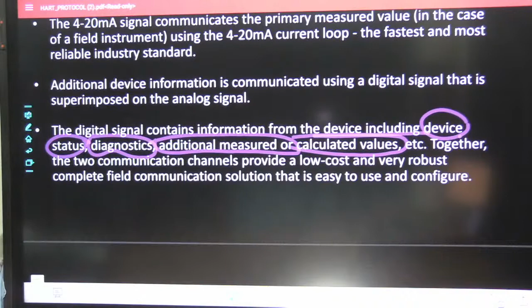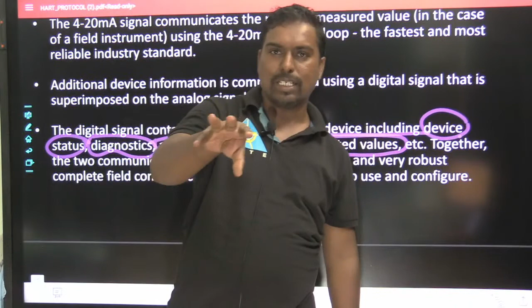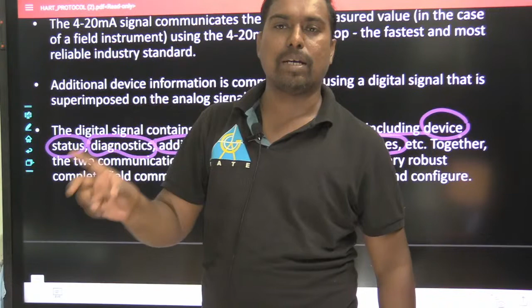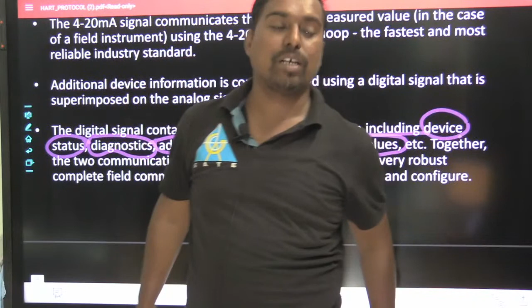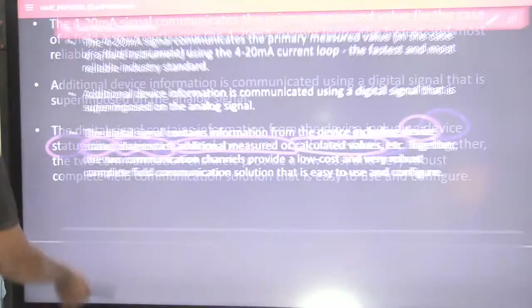Okay, do you understand what I mean? No, not different ports, my dear. They are traveling on the same 4 to 20 milliampere signal, but I am configuring the sensors. By using the HART settings, I am configuring the sensors so that when configured, automatically the data is coming from the temperature. That is what I am telling. On the same wire, we are not having multiple 4 to 20 milliamperes wires. We are having a single channel of 4 to 20 milliamperes. On the single channel, we are mapping the different digital information. Got it? That's it. Yeah.